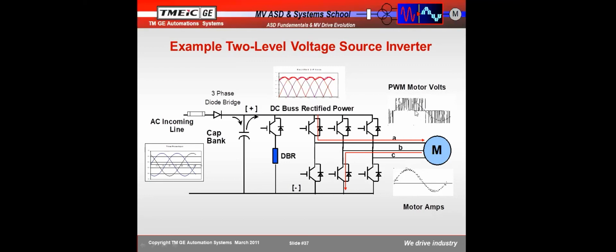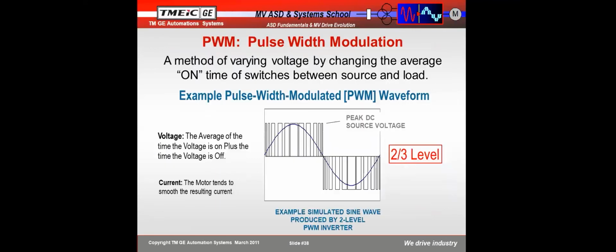And basically you've got this picket fence where you're just turning that voltage on and off and on and off, and you can turn it on and off in the positive direction and the negative direction. And by using PWM technology, varying the width of those pulses, you get a current waveform. That's not a great voltage waveform, and we have a lot of problems. That voltage waveform is the reason why we have to have higher insulation on low voltage motors, because it creates really high voltages. You're going from 0 to 650 volts almost instantly, I mean very quickly, and that causes some real problems with our insulation. But all low voltage drives are built that way. That's just the way the world is.